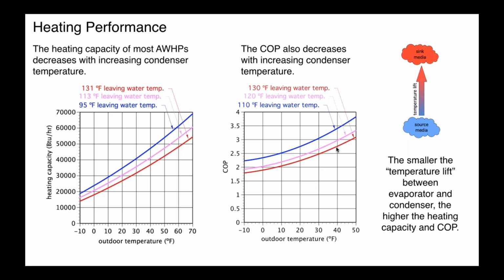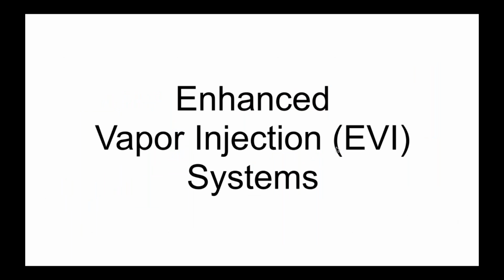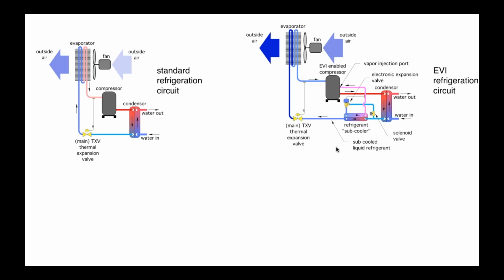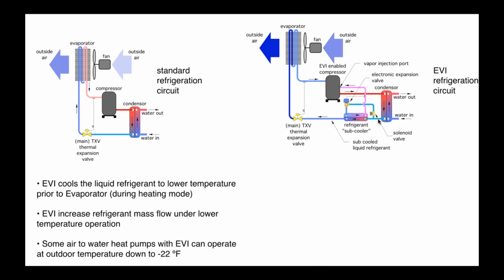Okay. So again, think about temperature lift. You can't control outdoor temperature, obviously, but you can control to some degree the water temperature that's necessary in that hydronic distribution system. Okay. I just want to mention real quick what are called EVI, or enhanced vapor injection systems. Really quickly, what an EVI system does is it lowers the temperature of the liquid refrigerant coming out of the condenser. It lowers it farther than a standard refrigeration system can. And you might say, well, so what? What does that do? Well, it means you can absorb heat from even lower temperature outdoor air.